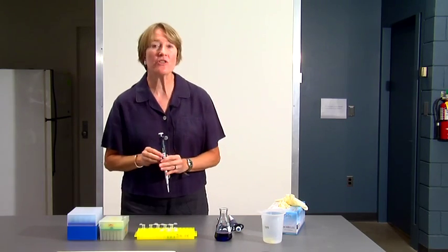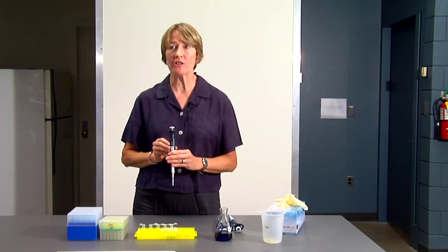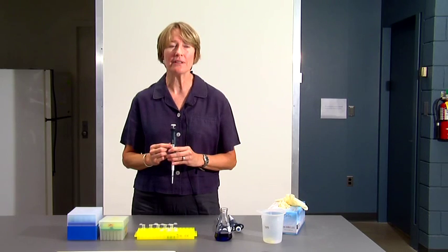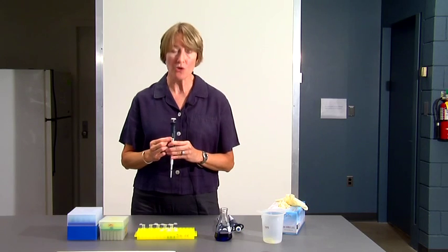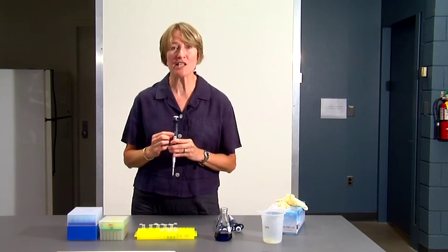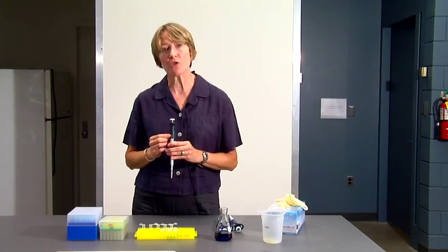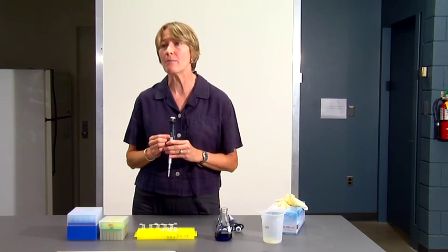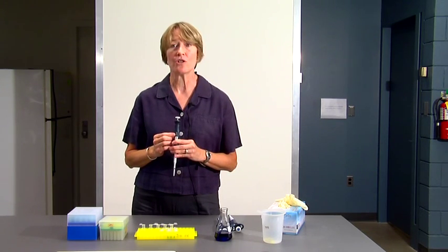The third pipet that we'll be using is the P20, which measures accurately 2 microliters to 20 microliters. This also has three numbers on the barrel. But notice that the bottom number is in red. That is an alert that tells you that bottom number is tenths. So there's a decimal point before that number. So if the dial reads 100, that stands for 10.0, or 10 microliters. If you wanted to measure 2 microliters, you'd set the dial on 020.